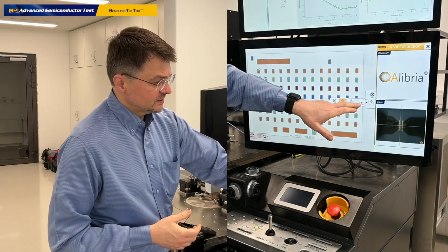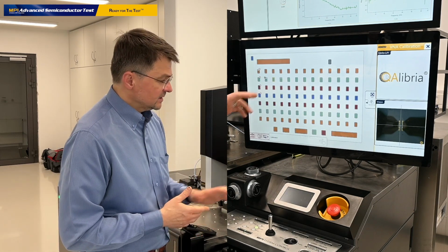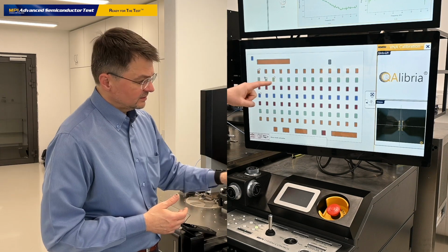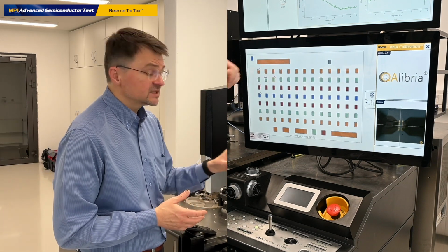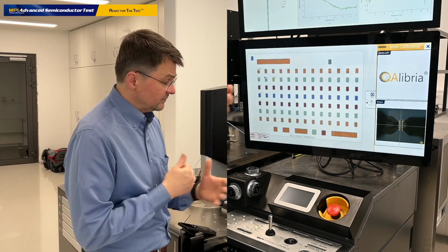So just simply change the tool used for the cal, not move to, but used for the cal. And after that, I just click on this calibration standard, and you see a kind of red circle around the standard. It's a marker that shows us that this particular standard will be taken for the calibration process.